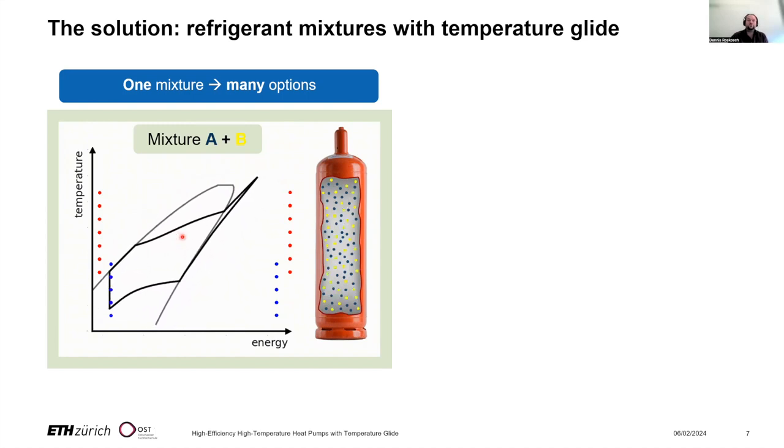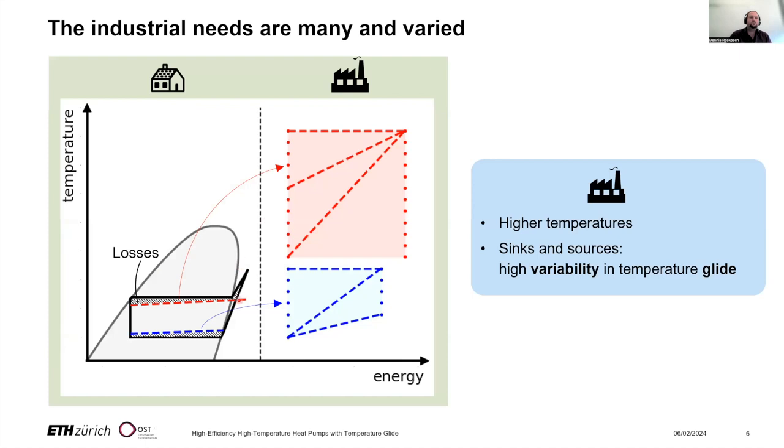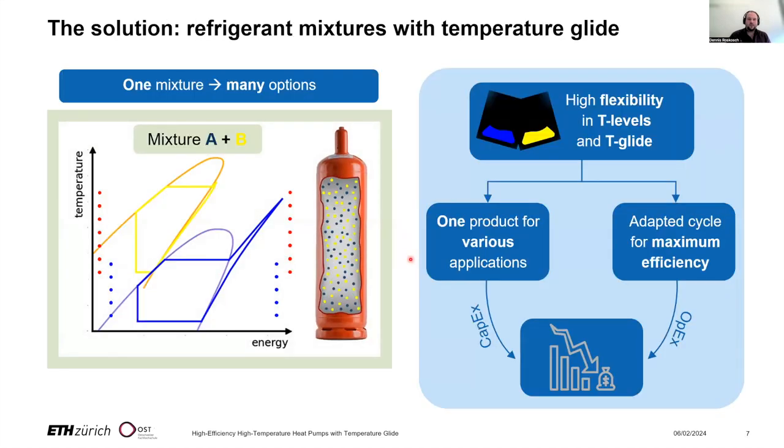This is particularly beneficial when the temperature change of sink and source is large, which is often the case for industrial applications. If we use a pure refrigerant with isothermal condensation for such a heat sink, we end up with a very large irreversibility area. But with a mixture whose phase-change line follows the shape of the source, we can reduce that area and increase efficiency. By using mixtures and tailoring the composition, we can increase efficiency, flexibility, and standardization — because one product engineered for one binary mixture can be efficiently used for many applications just by adjusting the mixture composition.